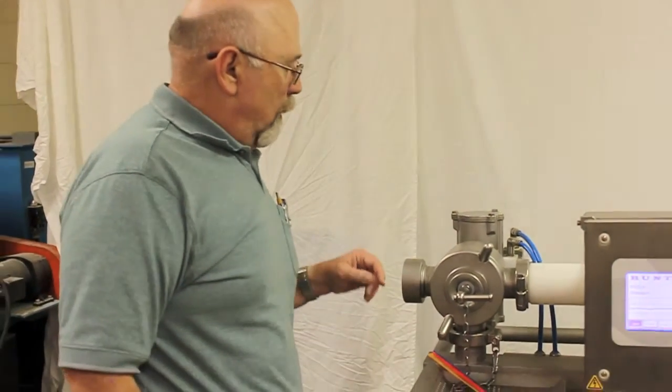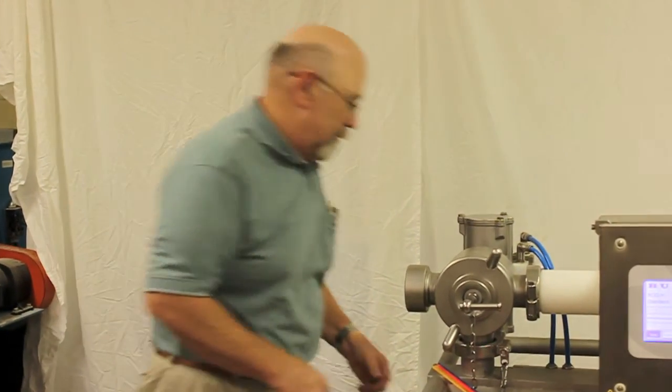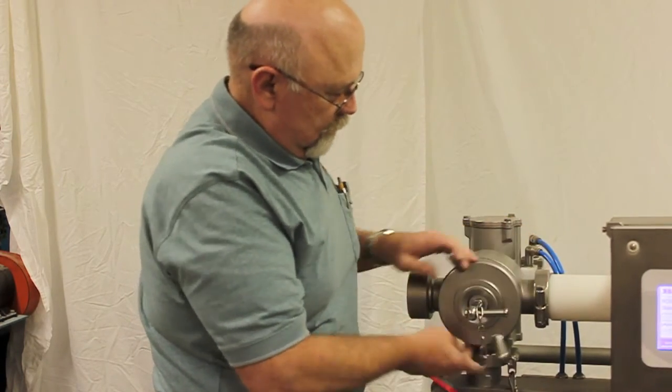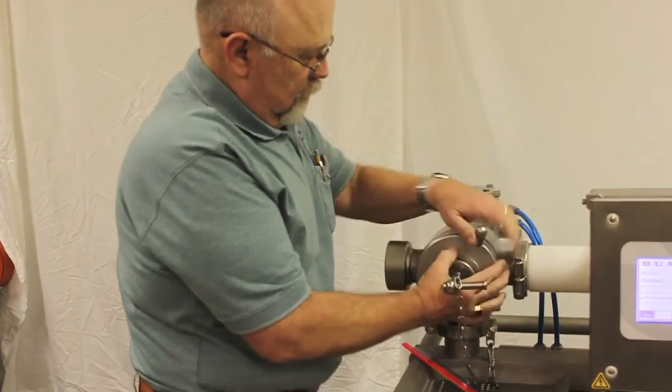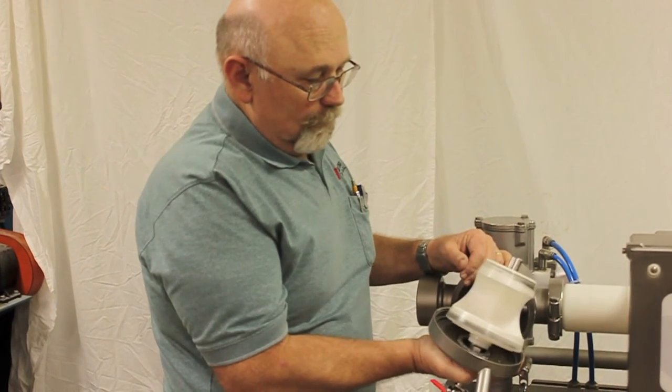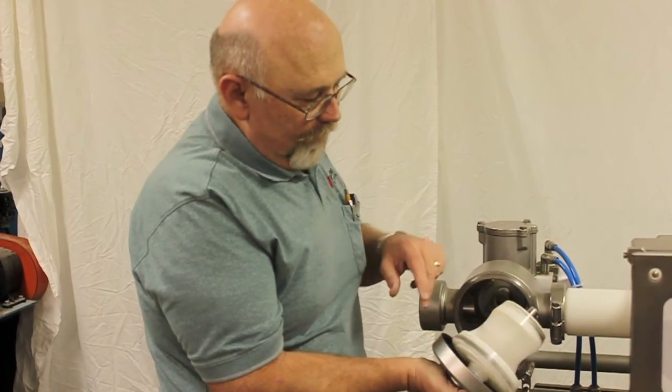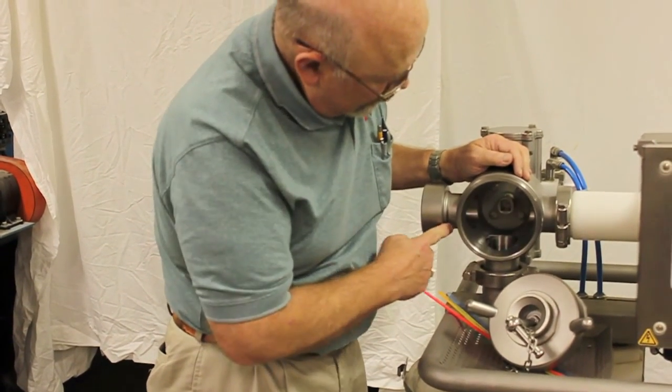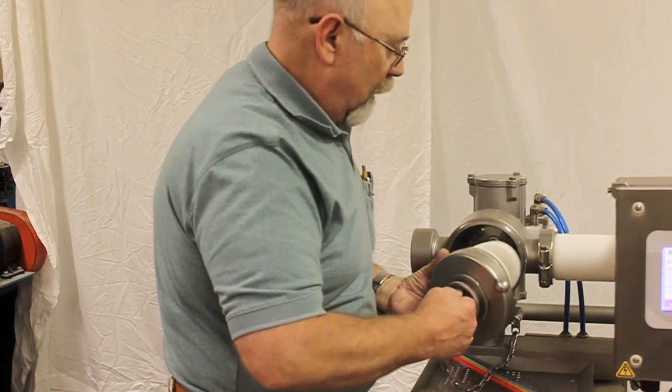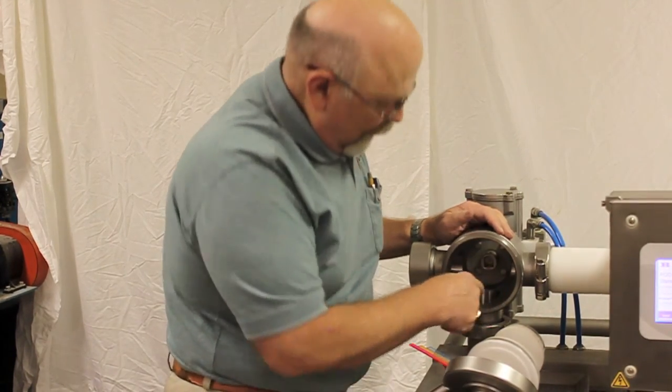So we're going to take this unit apart. First thing we're going to do to be safe is we're going to release the air. So our air is released, and now we're going to open up this housing right here. And as you can see, it's very easy to take that housing apart. This is your diverter valve here. This is the housing on the inside. You can see where the good material will come right through here. And then as this diverter valve changes position, it will divert the contaminated material right through this port here and down into the waste bucket.